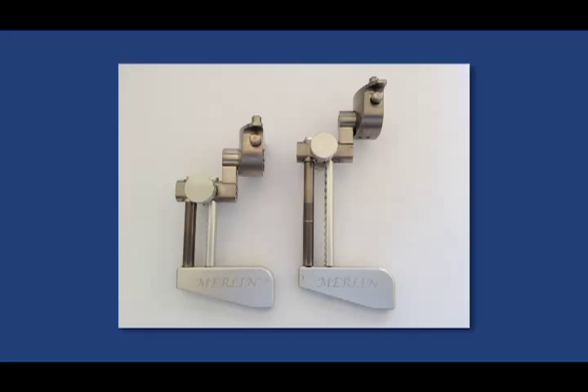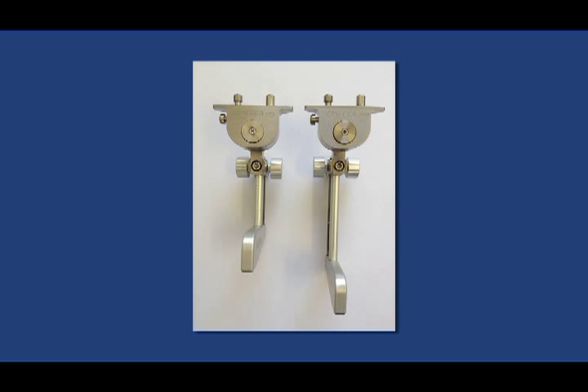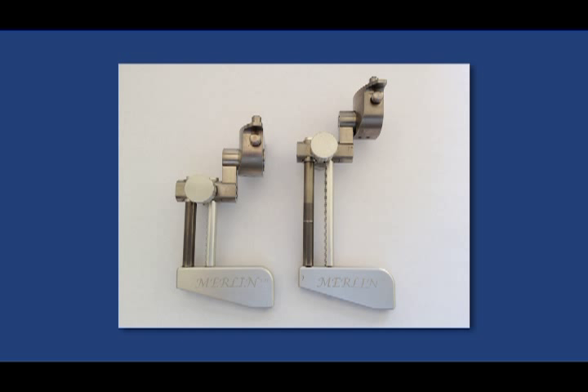There are two different LPUs designed for use with a Merlin CLA. The exact LPU required for your system will be determined by whether your microscope objective lens has a 175mm or a 200mm focal length. It is important to note that the LPUs are designed for use with a specific focal length objective lens, either 175mm or 200mm. The LPUs are not interchangeable, therefore it is very important to confirm the correct LPU for the objective lens focal length.